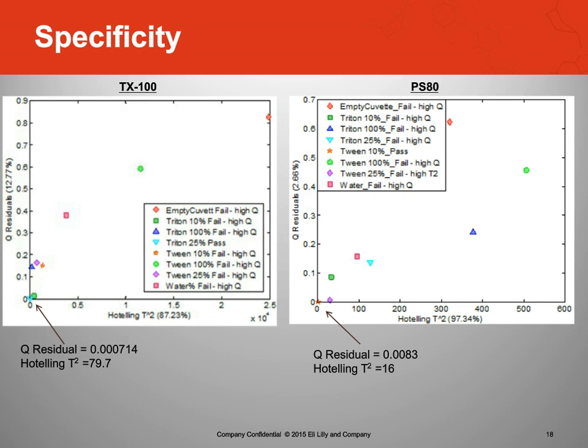So we're able to capture any type of improperly prepared material when running the Triton method, and the converse is true as well. Empty cuvette: what if they prepped Triton instead of tween and ran it? It would fail at the high Q. If you ran Triton at 100%, that's more of a control to show it fail. And Triton at 25%: what if they ran the wrong method? If they prepped Triton at 25% and ran it on tween, we'd fail. Of course, the controls pass, and so forth. And obviously water, if they ran water, it would fail. So the specificity is very discriminating between the samples, so the model is capable of determining whether or not you ran the right material.